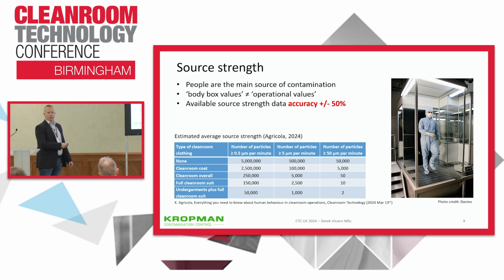Agricola from the Netherlands presented a table with average source strength values for different types of cleanroom garment, for 0.5 micron, 5 micron, and 50 micron. But he also stated in this article that the accuracy of those values is plus minus 50%. And in one of the latest webinars, he also mentioned that when the activity levels are much higher, those values can be up to 3 or even 4 times higher. So for us as designers, still difficult to design on.